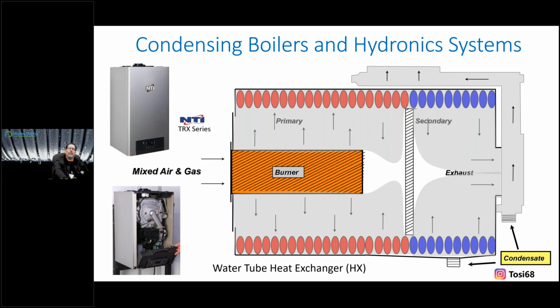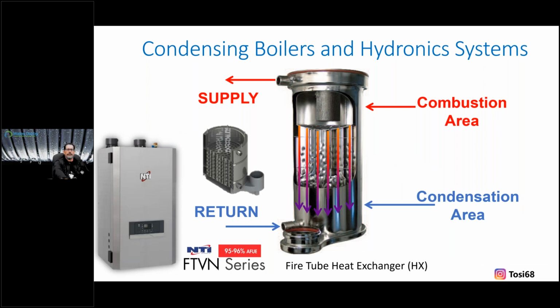What exactly are we getting out of all that washing of condensation coming back from our flue products? So here is no different. At the top is our supply. That's the hottest water going out, if it's going to our low loss header, hydrosep, closely spaced tees, and our piping, and the bottom is our return. So you see the coolest water against the hottest combustion, and that's how we're going to transfer all our heat energy, okay? And that's really the crux of why you're doing what you're doing. Yeah, I've seen some hiccups, some bumps in the road, and maybe even some maintenance issues. We've got to get better at that. But if you see the advantages of just lowering your water temperature or spreading out your delta T on your systems, these are all the benefits of what we've been doing in that first slide. We've been doing a lot, but I guess we're just missing that one extra step, lowering water temperature, all right?